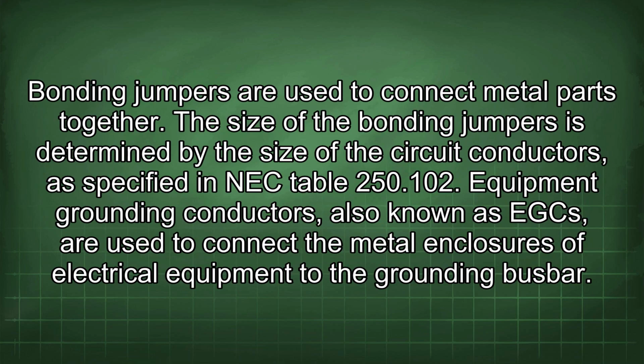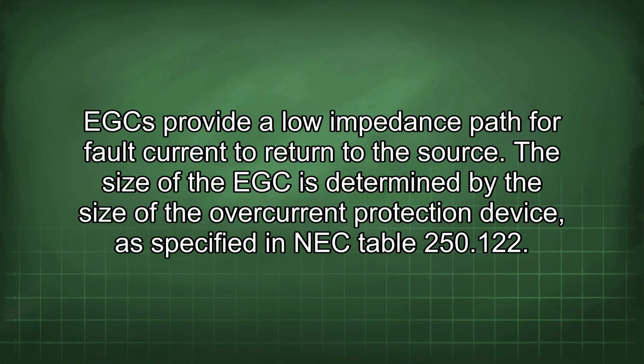Bonding jumpers are used to connect metal parts together. The size of the bonding jumpers is determined by the size of the circuit conductors, as specified in NEC Table 250.102. Equipment grounding conductors, also known as EGC, are used to connect the metal enclosures of electrical equipment to the grounding busbar. EGC provide a low impedance path for fault current to return to the source.